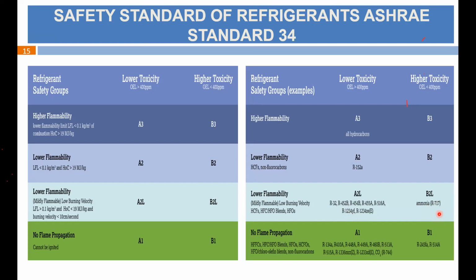Ammonia comes under higher toxicity and lower flammability. Ammonia has good thermodynamic properties, but the problem is its higher toxicity. That's why its safety class is B2L, and it becomes poisonous at very high concentration. When the concentration of ammonia is high, it becomes poisonous. So that is one of the disadvantages of ammonia. Otherwise, it has very excellent refrigerant and thermodynamic properties.